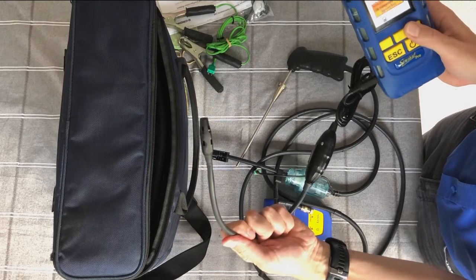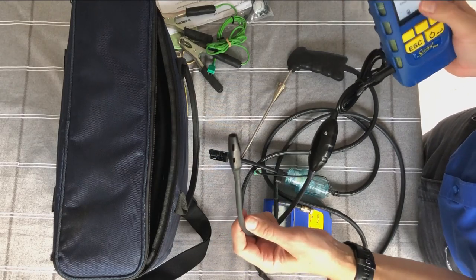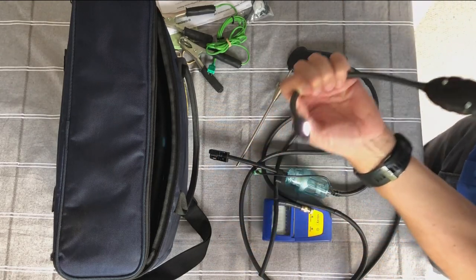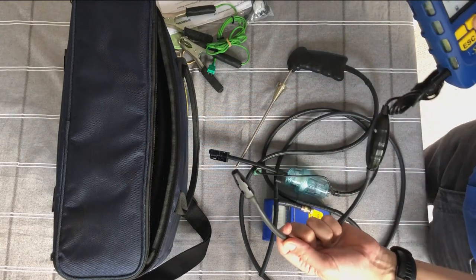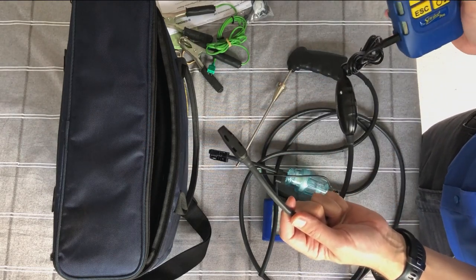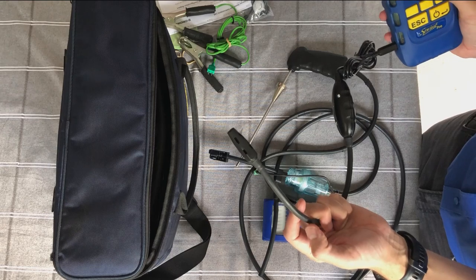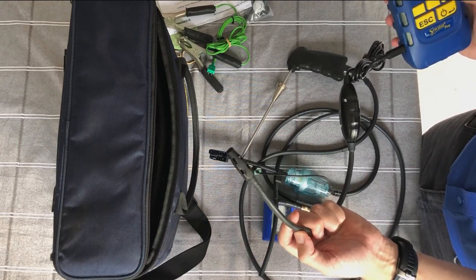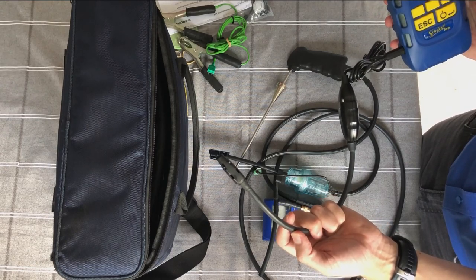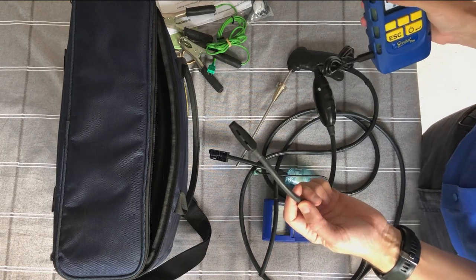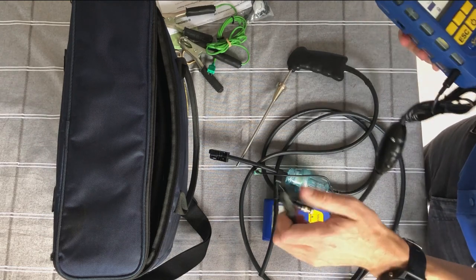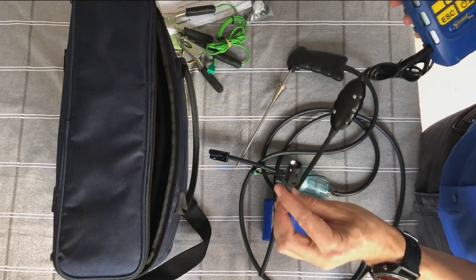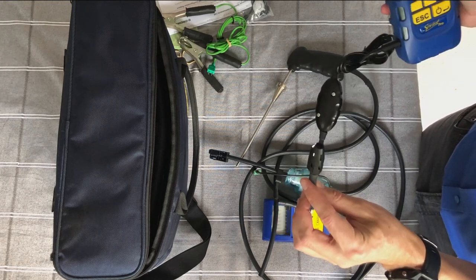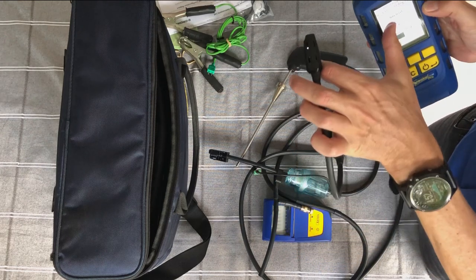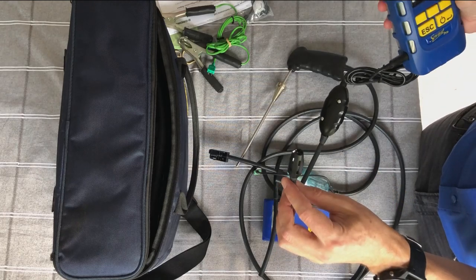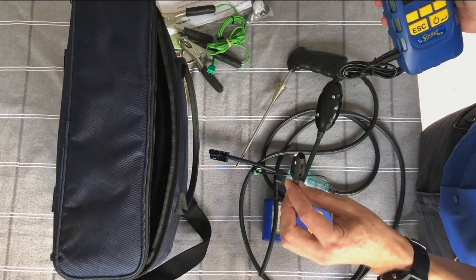You go into gas escape detection mode. It says ensure wand is connected, which obviously mine is. There's a little light in the end, if you can see that, to help you see in the dark. It's just checking the sensor. It takes about 30 seconds to settle and warm up, and then you're basically reading gas. It doesn't give you an exact parts per million or percent volume of flammable gas, but it gives you an indication of how much you're seeing, from low through medium to high, and there's a colour band that comes across.